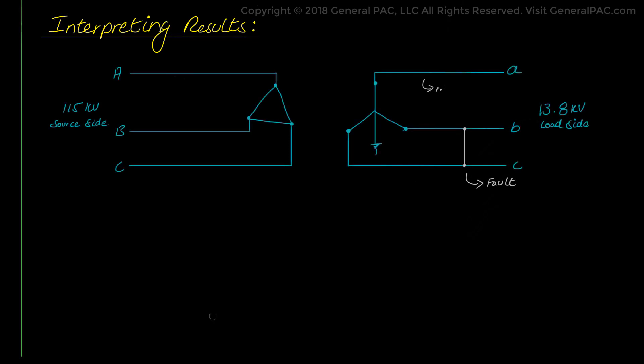especially if we consider our original drawing as shown. We know that phase A on the 13.8 kV system is the non-faulted phase and therefore it will not exhibit any fault current. However, phase B and phase C are the faulted phases. We have proved previously that phase B and phase C fault current will be equal in magnitude. However, it will be opposite in direction.